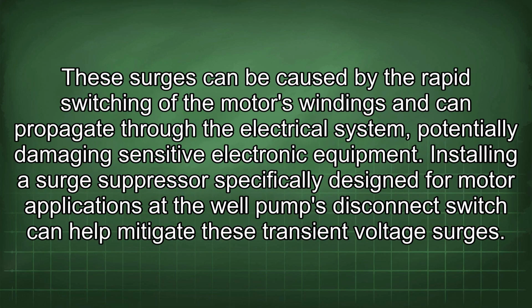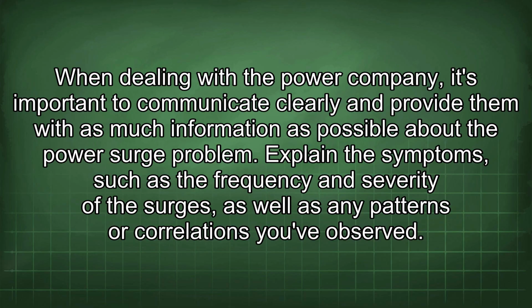These surges can be caused by the rapid switching of the motor's windings and can propagate through the electrical system, potentially damaging sensitive electronic equipment. Installing a surge suppressor specifically designed for motor applications at the well pump's disconnect switch can help mitigate these transient voltage surges.